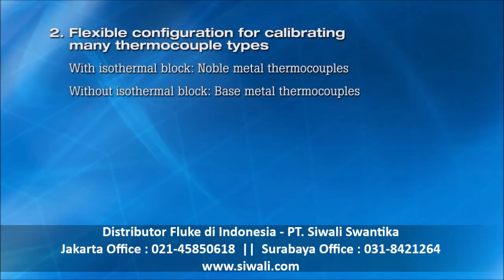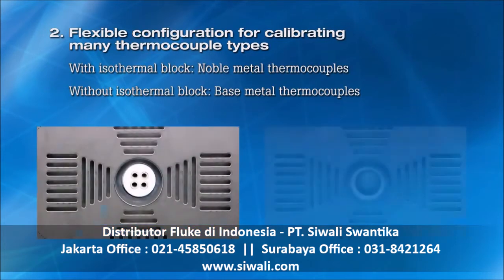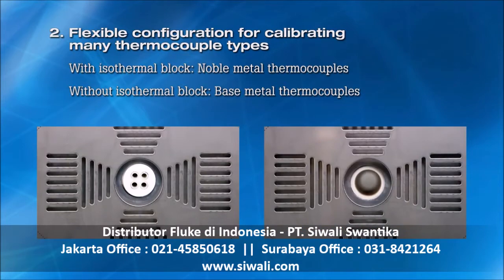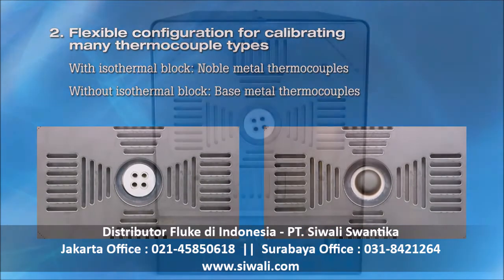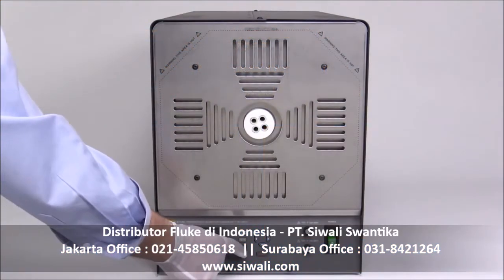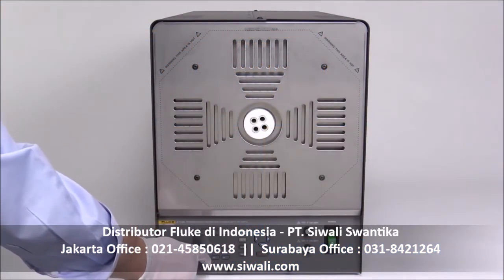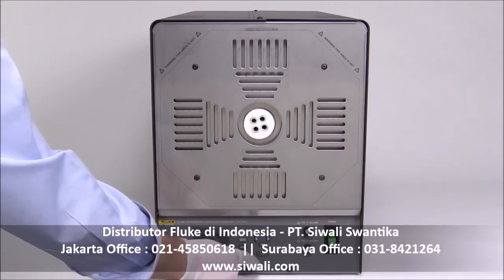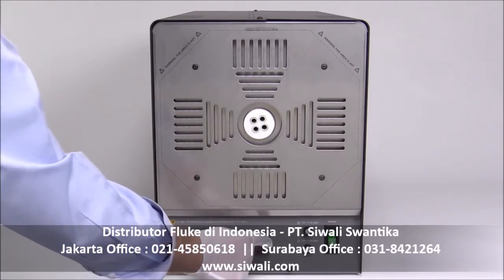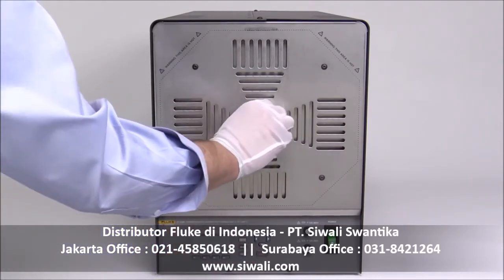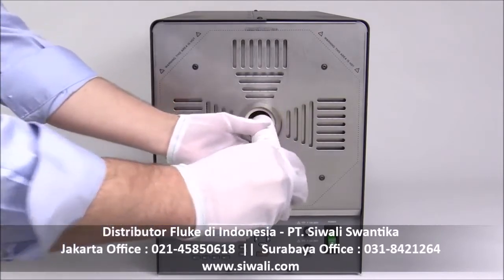Second, flexible configuration. The 9118A furnace can be operated with or without an isothermal block, which increases the calibration workload that can be performed with a single furnace. The furnace configuration can be quickly changed by selecting the calibration parameters stored in the controller for the desired configuration and inserting or removing the alumina-ceramic isothermal block.